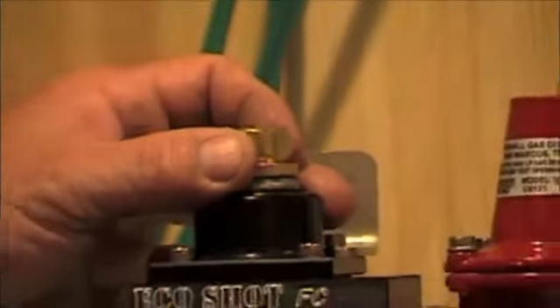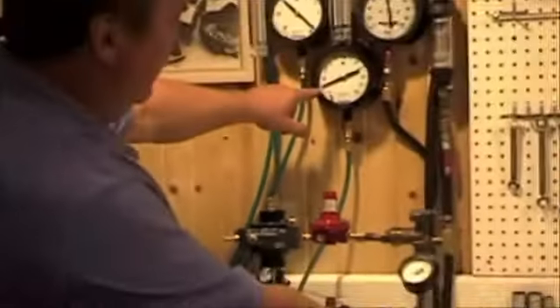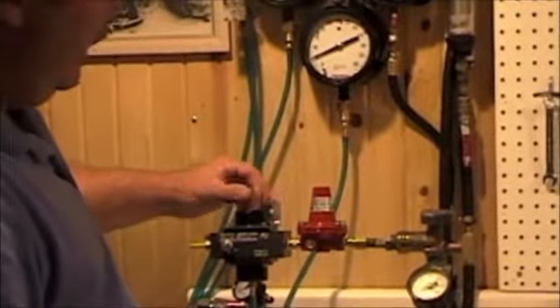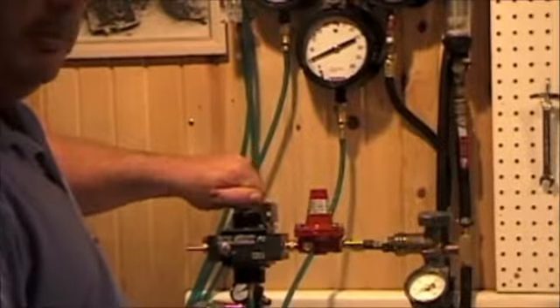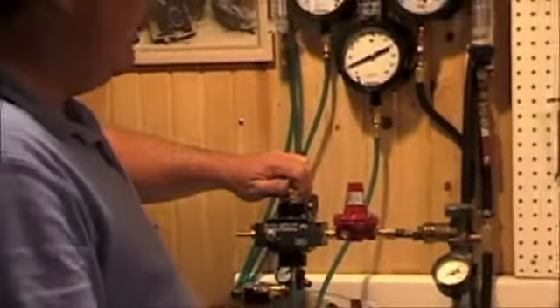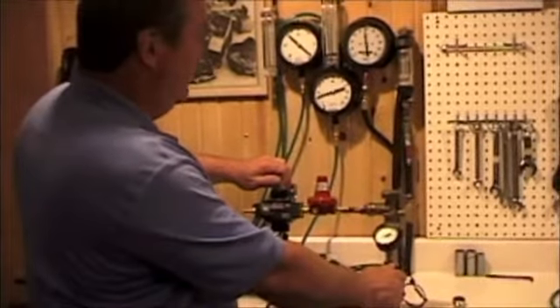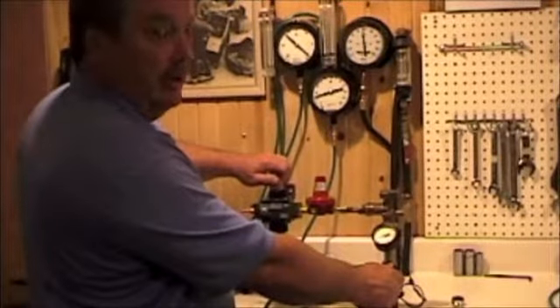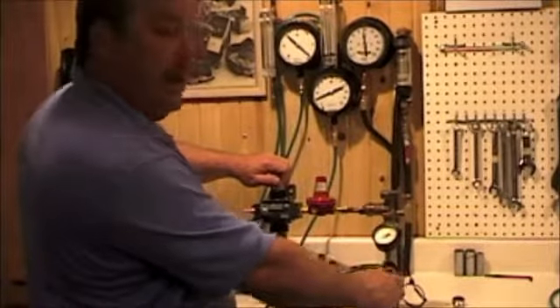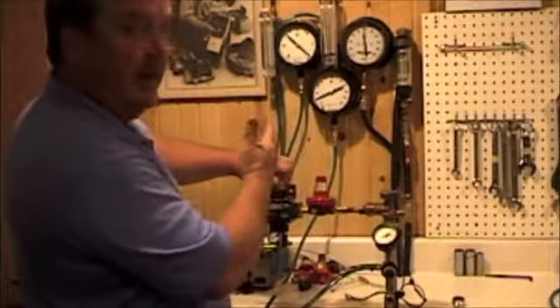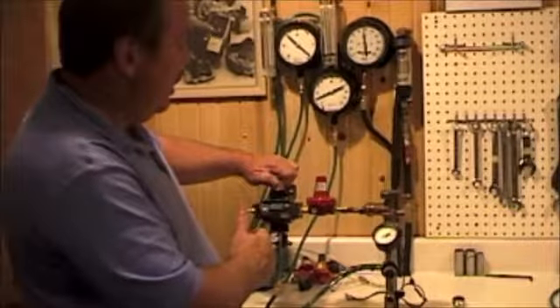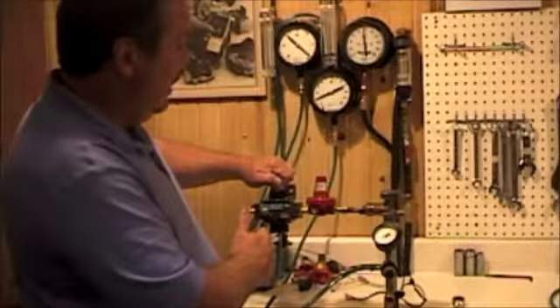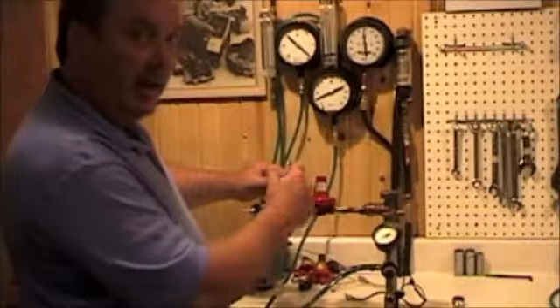What you would do is apply 5 pounds of air pressure. As you can see here, we have 5 pounds. Now we can turn this valve, and I can stop that flow of propane altogether, where it's not flowing at all. Actually, I'll need to take it up to 7 to get it to flow. But if I want a 5 pound start time, I set it at 5 pounds of pressure. And then I back, I've already taken it, I had it shut off.